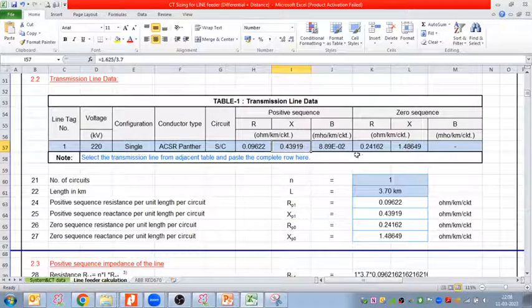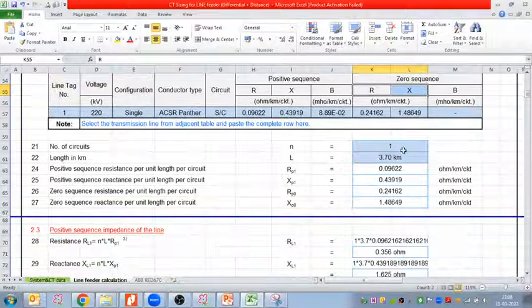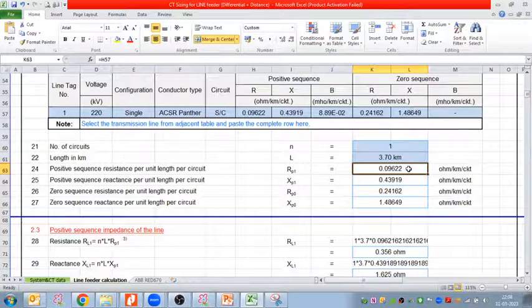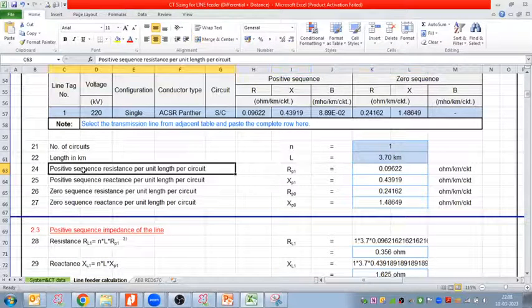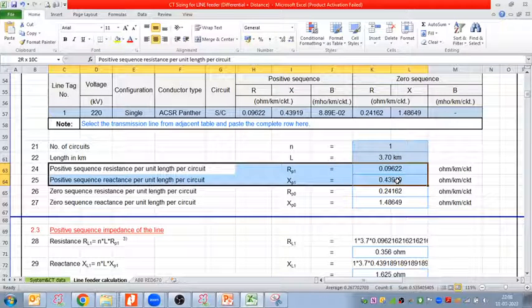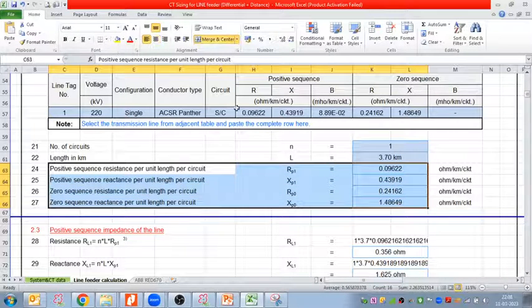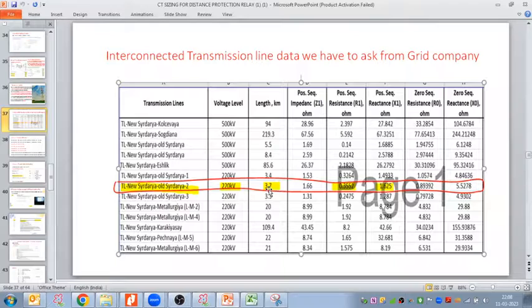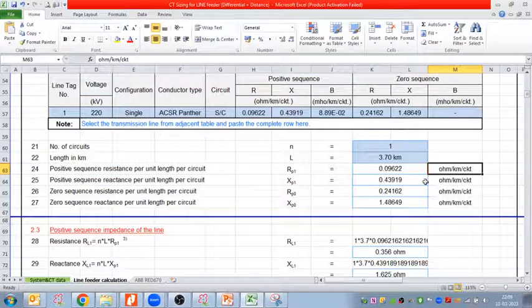So here we got the R, X, positive sequence and zero sequence. This value we put in this Excel. Number of circuits is one, length 3.70 kilometers. Here the positive sequence resistance is 0.09622 ohm per kilometer per circuit. So we calculated the total resistance now: positive sequence resistance, reactance, zero sequence resistance and reactance. Whatever the given value is, divided by 3.7 kilometers, it gives the per kilometer per circuit resistance and reactance.